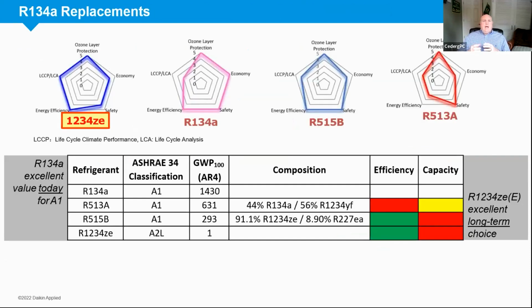That last slide would have shown something very similar to this. Currently, Daikin Applied has a replacement for 134A with 513A. Again, it's a lower GWP compared to 134A, at 631. It is a blend. Unfortunately, we lose some efficiency and some capacity with this refrigerant, but it's something we can move forward with today on both our screw and centrifugal compressors.